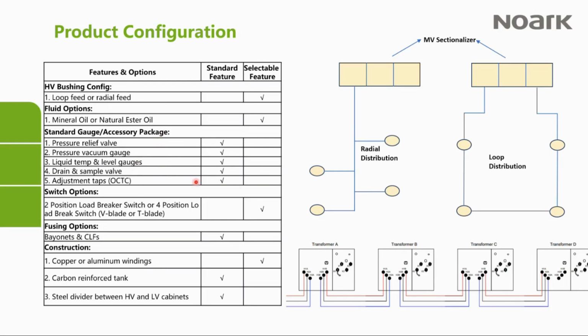The other part that I should mention also, we keep talking about the bushing configuration. We say we have the loop type and the radial type. Now, this talks about the type of supply that you will get in the area where you want to install the pad mount transformer. So if you have a radial distribution, this picture explains what that means. From your MV sectionalizer, that's from the utility or wherever you're getting the supply from, you're going to have a single conductor, right? And then from there, you have tapped off to the individual pad mount transformer like this. So in this case, you have four pad mount transformers using a radial distribution. You can see it's coming from a single source, and then it's tapping off to each of those pad mount transformers.